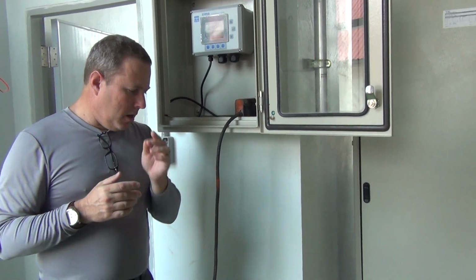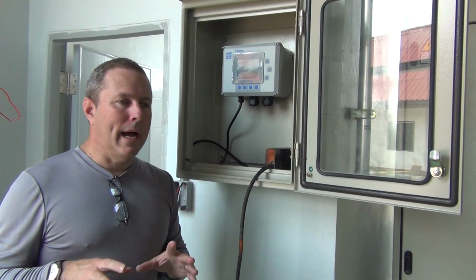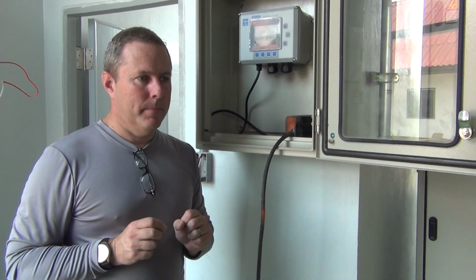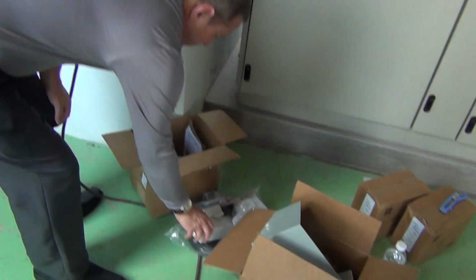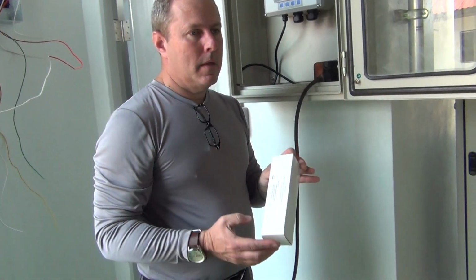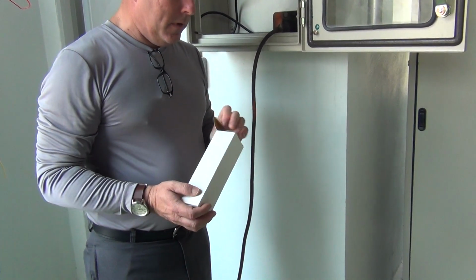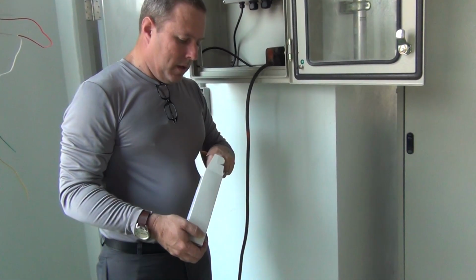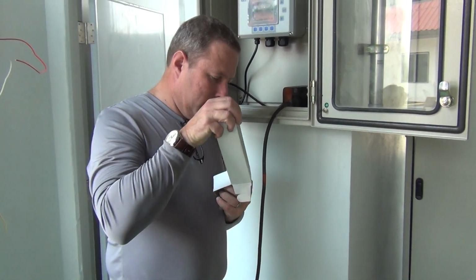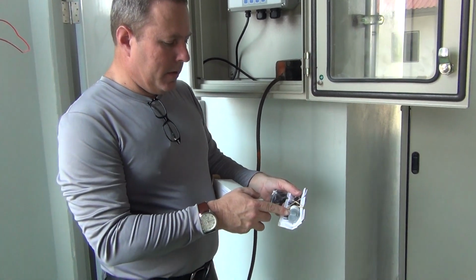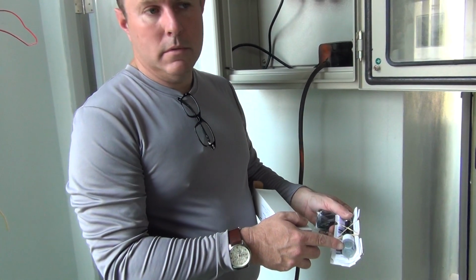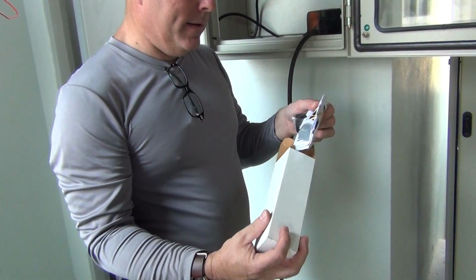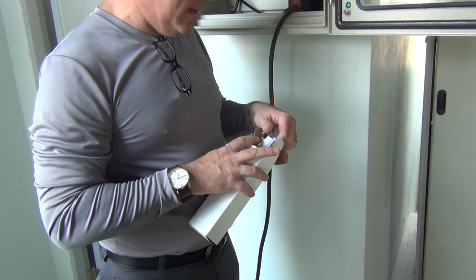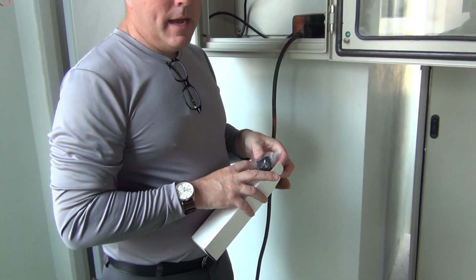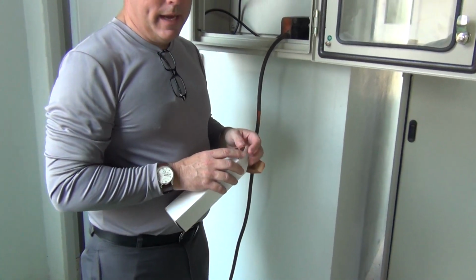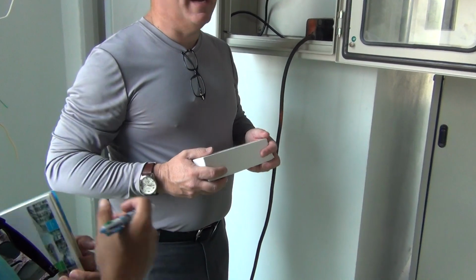During the dry season, all of the probes are okay dry, except the pH/ORP probe. This one probe has to stay wet. If you don't keep it wet, the glass bulb inside would break and crack. So you see how it's shipped wet in electrolyte? In the dry season, we can remove this probe and put a cap in its position, and then it's okay. But then you would not have readings of pH and ORP.